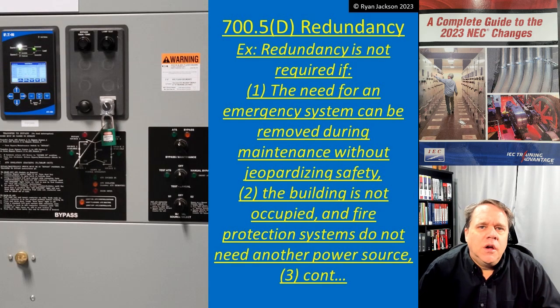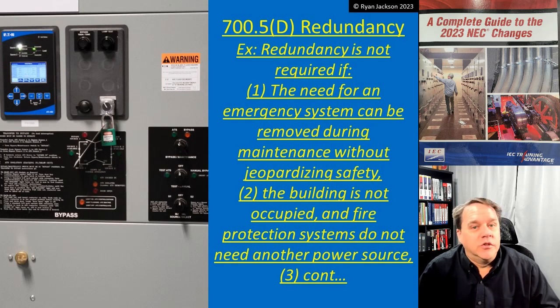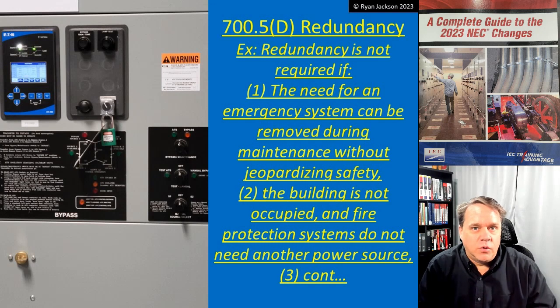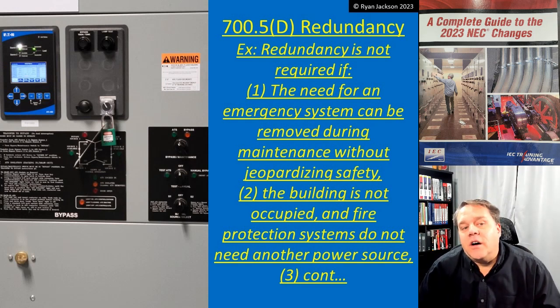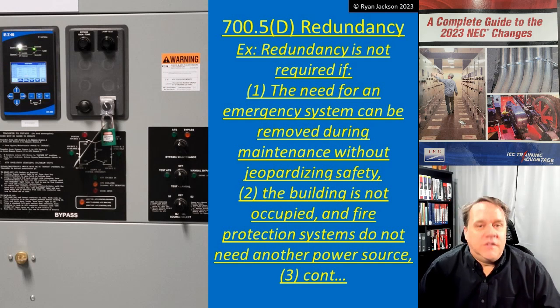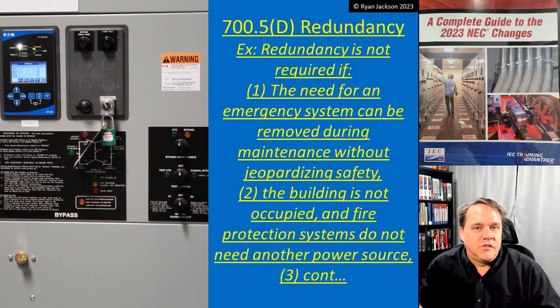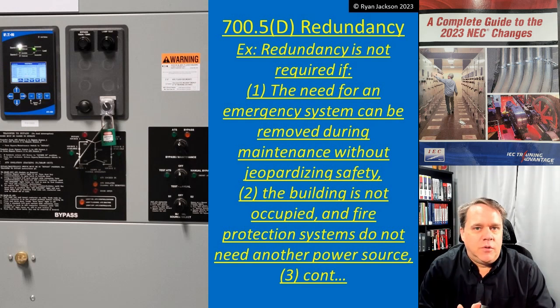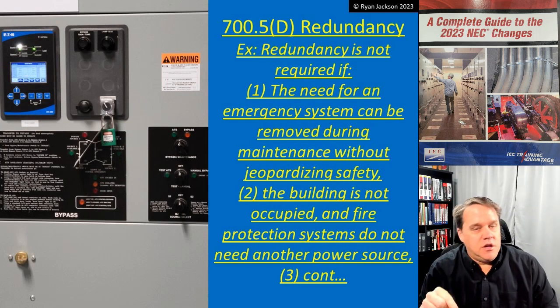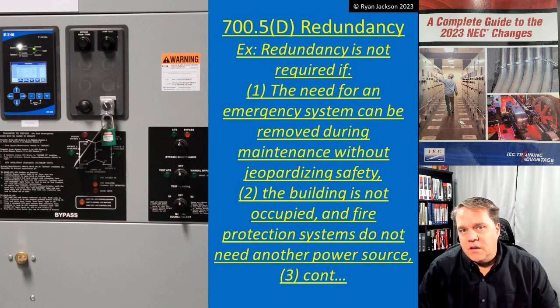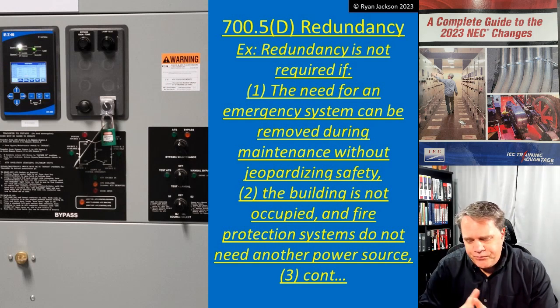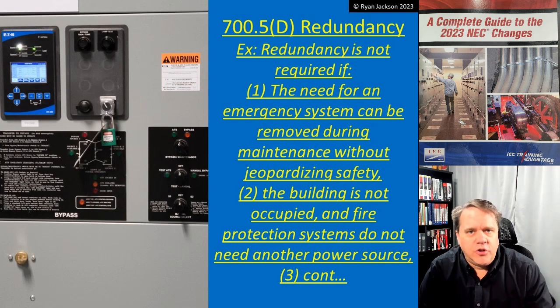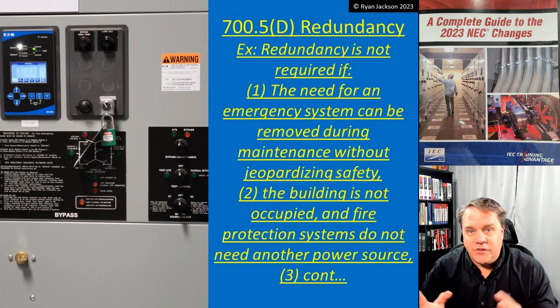One place I consult for shuts down the entire plant once a year during the 4th of July weekend — except for the electricians, who do all the maintenance on the facility that weekend, including testing and repairing the emergency system. The need for the emergency system at that facility might just be emergency lighting, and you don't need emergency lighting in a building that's not occupied. You could potentially meet this exception, but you'd need written requirements to show the inspector. In most applications, you won't be able to meet this exception — most places can't completely vacate the building long enough to do maintenance.